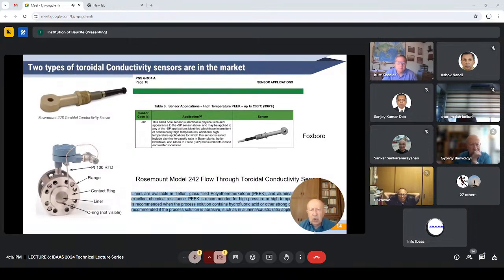Here there are two types of conductivity sensors in the market. This is the embodiment of the Rosemount toroidal conductivity sensors. The other is practically the same by Foxboro, and in the leaflet it is highlighted that it has been used in various alumina refineries for alumina to caustic ratio control. The other type of these toroidal conductivity sensors is the flow-through toroidal conductivity sensor. This is also being used for alumina to caustic ratio control.